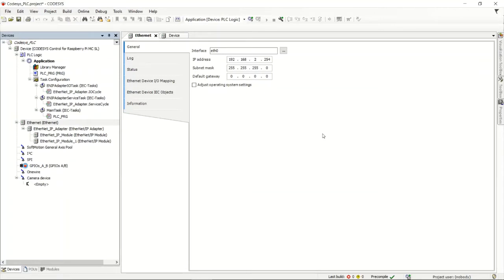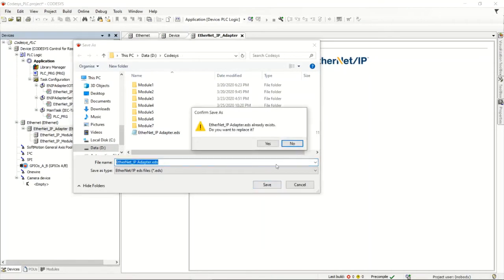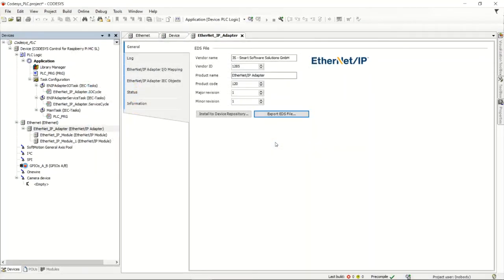That's my Raspberry Pi connection. From there I'll configure the adapter by double-clicking on it. There's no configuration for the adapter itself — it just does its job — but you want to pay attention to the product code, major revision, and minor revision. We'll take advantage of the Export EDS File button. You can make a custom EDS file by pressing that button, which creates the EDS file to import into RSLinx. Electronic Data Sheets identify the hardware, give it its icon, and tell RSLinx the product code, revision number, and so on.